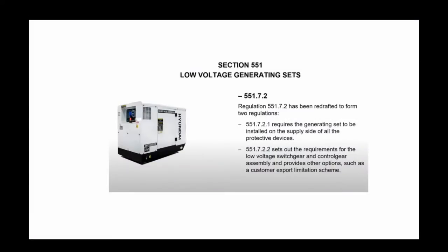So we've now got 551.7.2.1, and basically what that's saying is it requires the generator set to be on, and I don't like the wording in here, and this is a good suggestion for your viewers to put a comment on this because I think this is really complicated for people to understand. It says, requires the generating set to be installed on the supply side of all of the protective devices. Well, what it actually means is it needs to be on its own circuit. So you can't put the supply on another circuit. Ah, okay. Well, yeah. Thank you.